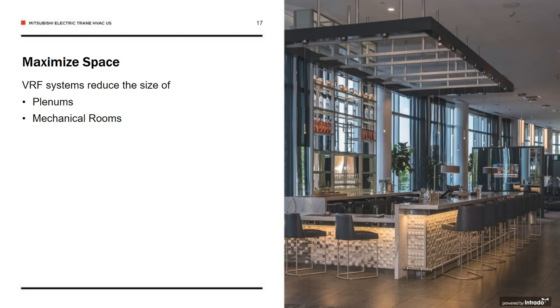First, let's look at maximizing the space. VRF accomplishes this in a few ways. One, in reducing the size of the plenum required. Less bulky ductwork can lead to a plenum reduction of 6 to 8 inches depending on your application and the floor type that you're targeting. Also, depending on the application, you can completely eliminate the mechanical room.